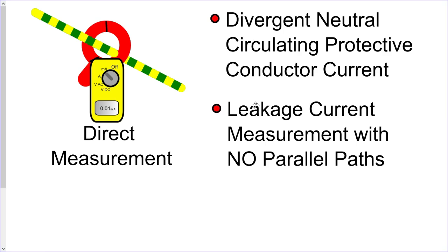Well, generally, health and safety. For yourself, when you're carrying out inspection and testing, remember you might be disconnecting these big green and yellow wires in your installation. So we're looking for divergent neutral conductor currents, these circulating protective conductor currents that might be flowing through your earthing and bonding arrangements. Okay, so obviously we carry out those measurements before we isolate the installation, and then carry out the measurements again to make sure that these currents have disappeared.